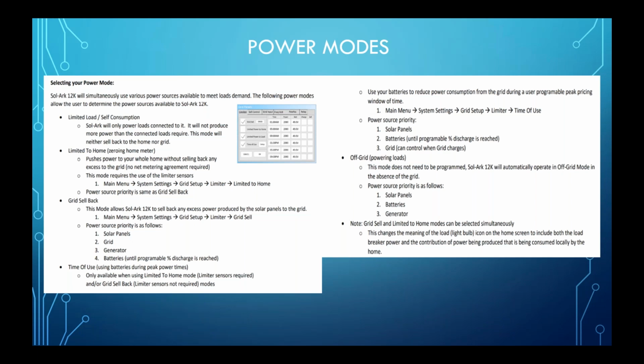Absolutely. There are very big differences between each mode, and you definitely want to make sure it applies to the project you're working on. For instance, the first one that you'll see selected is Grid Sell. If it is just a standard net metering kind of project, then having that set, it's going to produce as much power off the panels from the sun and send it back to the grid, and anything used by the time it makes it to the utility will be consumed, and then the leftovers will be sold back.